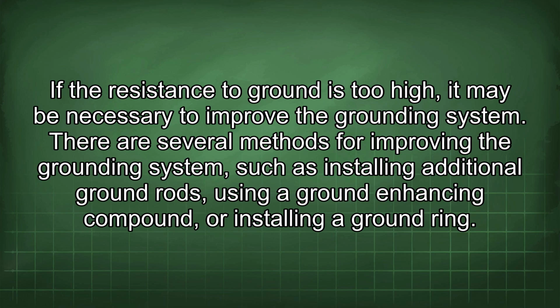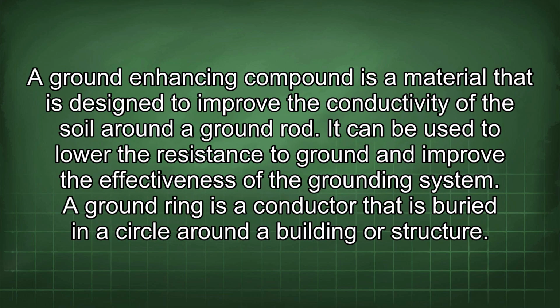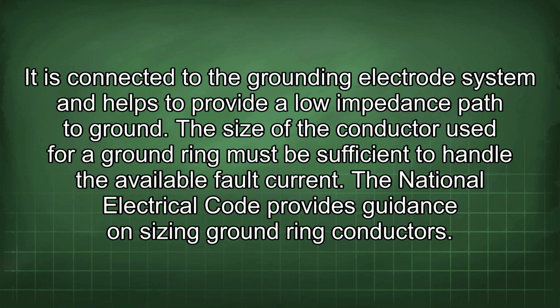There are several methods for improving the grounding system, such as installing additional ground rods, using a ground-enhancing compound, or installing a ground ring. A ground-enhancing compound is a material that is designed to improve the conductivity of the soil around a ground rod. It can be used to lower the resistance to ground and improve the effectiveness of the grounding system. A ground ring is a conductor that is buried in a circle around a building or structure. It is connected to the grounding electrode system and helps to provide a low impedance path to ground. The size of the conductor used for a ground ring must be sufficient to handle the available fault current. The National Electrical Code provides guidance on sizing ground ring conductors.